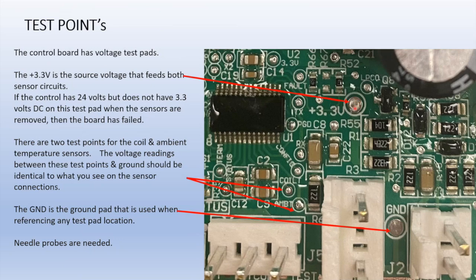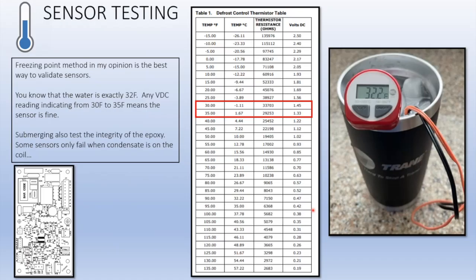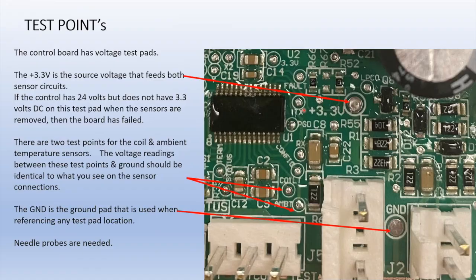Here you have a test pad for 3.3 volts DC, which is the source voltage for those sensors. You would test that against ground, because this board takes the 24 volt AC and turns it into 3.3 volts DC for your sensors. And then you also have test pads for your coil temp sensor and your ambient temp sensor, and you would check those with DC volts to ground and look at that versus this chart on the DC volts. So DC volts is connected to the board, and ohms is when it's removed from the board.